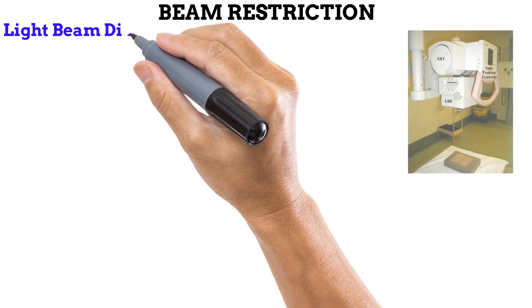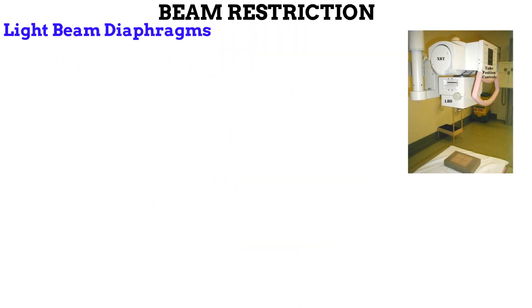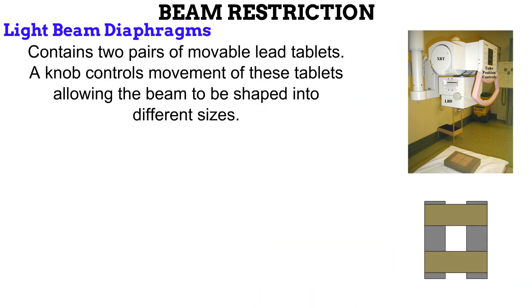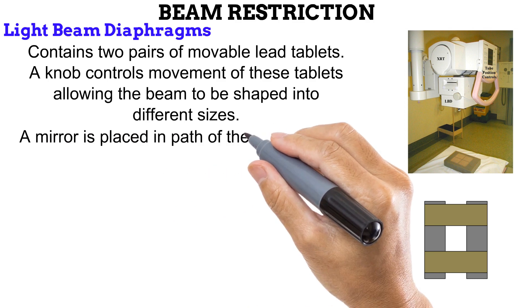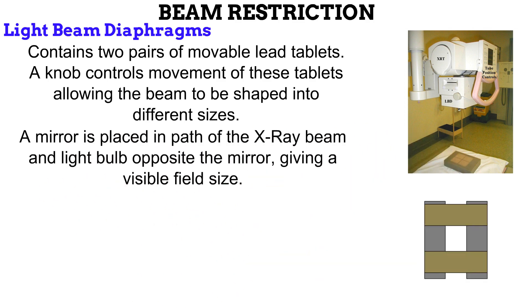Lastly, we have the light beam diaphragm, or collimator. It is the most advanced and sophisticated beam restriction device used in radiography today. It is fitted to the X-ray tube exit port. Inside the light beam diaphragm, there are two pairs of movable lead tablets. The gray knob on the light beam diaphragm controls the position of these tablets. By turning the knob, a pair of lead tablets are either brought closer or taken farther apart, allowing you to shape the beam into any size. Also, a mirror is placed inside the light beam diaphragm where it can intersect the path of the X-ray beam. A light bulb is placed opposite this mirror, enabling the radiographer to see the field size created by the collimator.